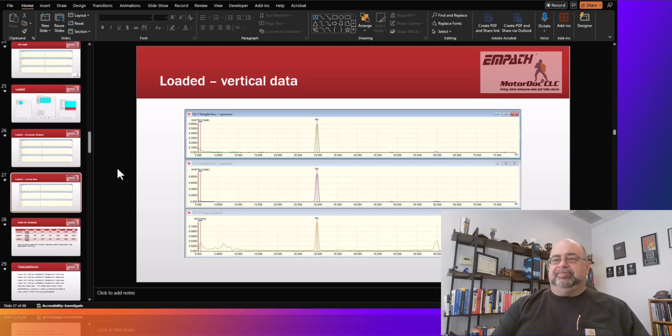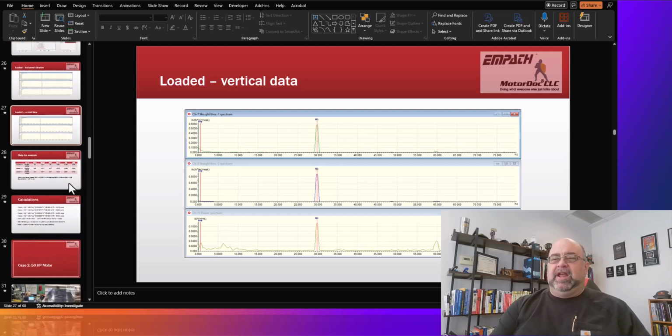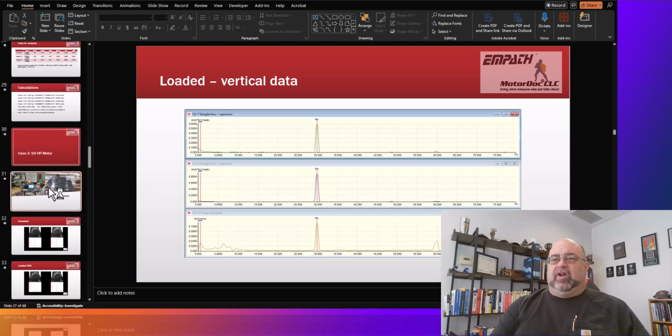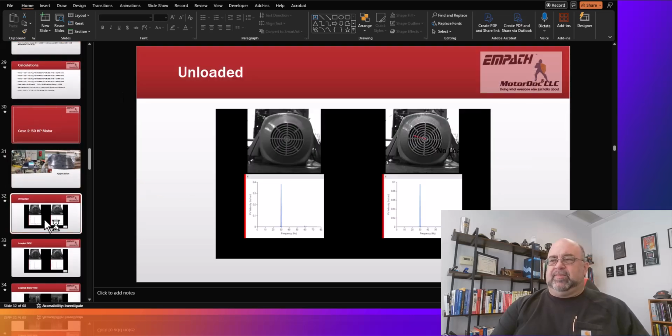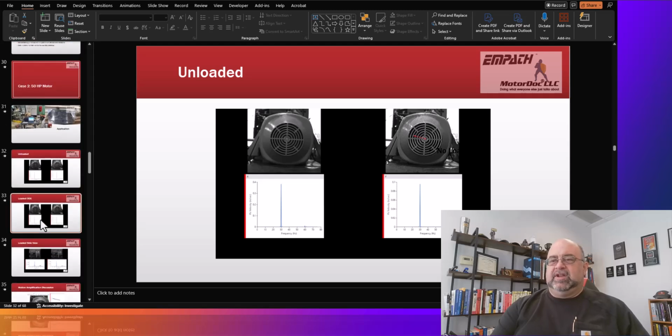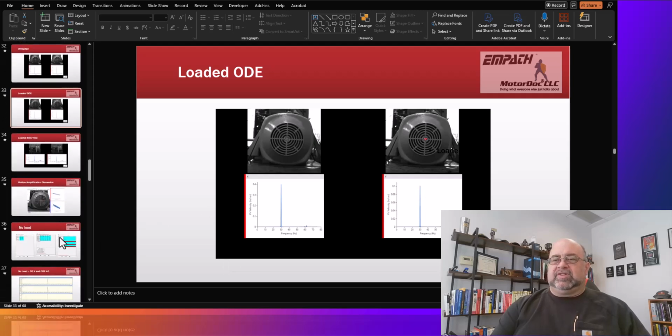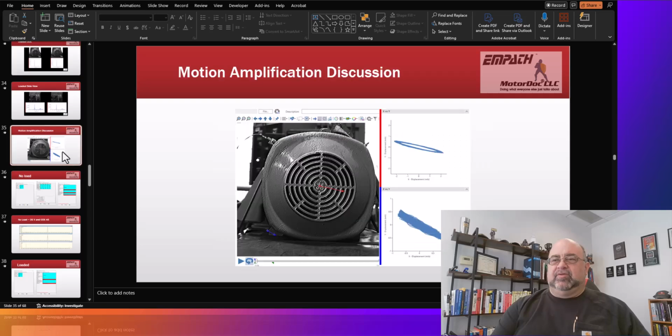But anyways, so the combination of stuff, right? So those are the values there. This one also had a slightly loose base. That one was vertical. This one's horizontal. The end result is my vertical readings are higher than my horizontal. My horizontal readings are higher than my vertical readings, as you can see here. Now, very low, and I did that deliberately. We selected very low readings so we could see what was going on.